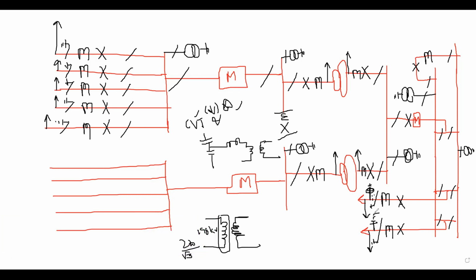See, sir, the PT is always placed on the buses to know the voltage signal. By seeing the voltage signal I close the breaker, so I have to place this PT before the breaker. Always the PT should be first when you are synchronizing, because by seeing the voltage signal you close the breaker. If you place the PT after the breaker, when the breaker is open, how can the PT see whether voltage has appeared or not? So in this case the PT will always be on the upper side of the breaker. Okay, sir, understood. The PT is installed first on the upper side because of the under voltage, fine now.